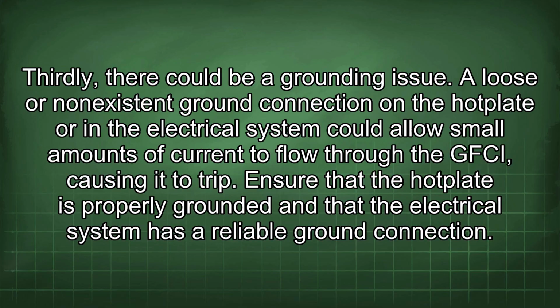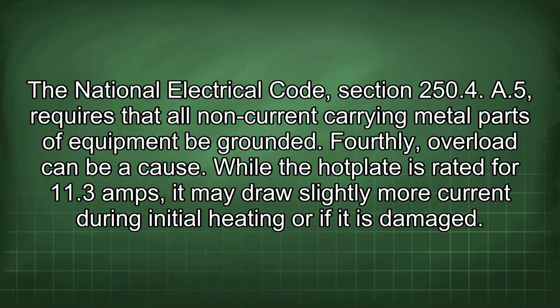Thirdly, there could be a grounding issue. A loose or non-existent ground connection on the hot plate or in the electrical system could allow small amounts of current to flow through the GFCI, causing it to trip. Ensure that the hot plate is properly grounded and that the electrical system has a reliable ground connection. The National Electrical Code, Section 250.4 A5, requires that all non-current carrying metal parts of equipment be grounded.